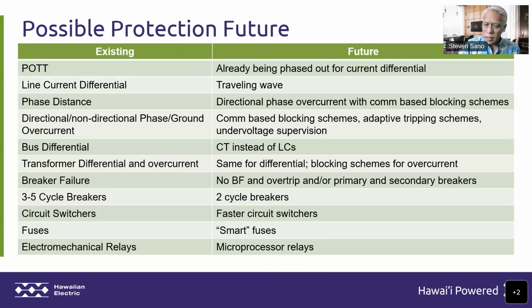So you can get them pretty fast nowadays, so possibly change to faster circuit switchers. Fuses, I mentioned fuses that are everywhere on our system. What do you do about them? Well, we do have programs to replace them with smart fuses, essentially electronic-based fault interrupting devices. Much more expensive than your common fuse, but much more flexible as well.